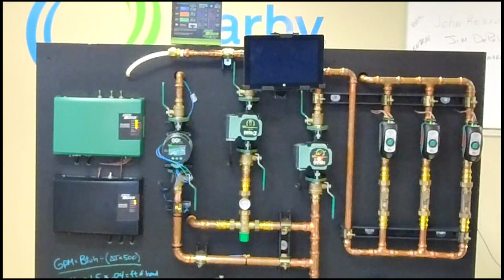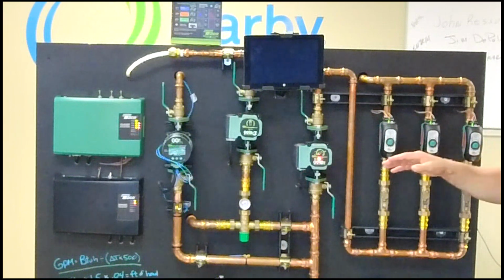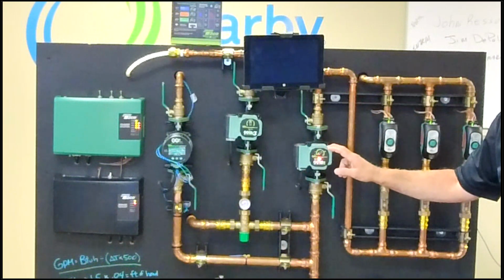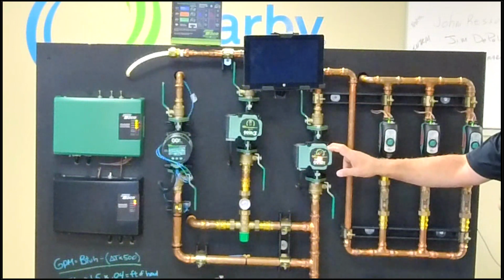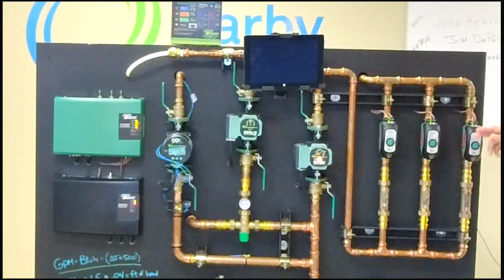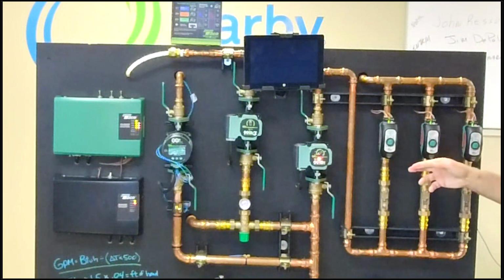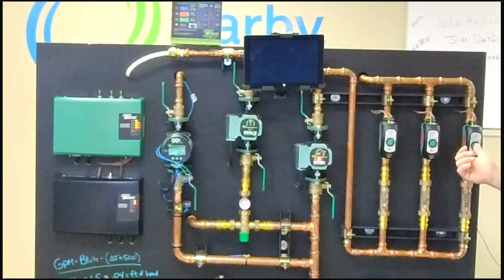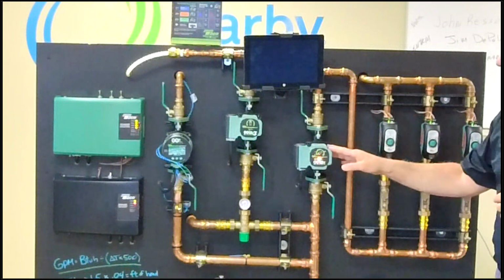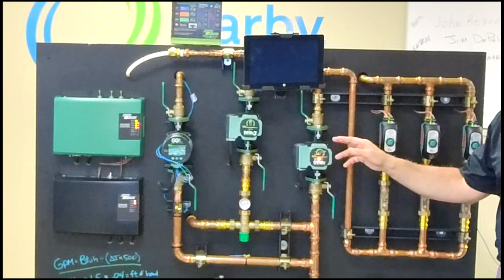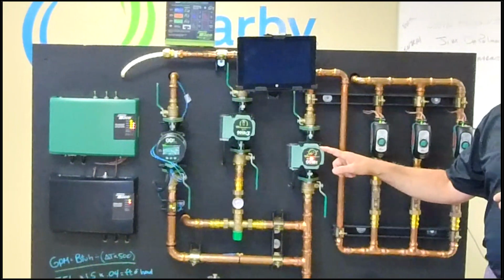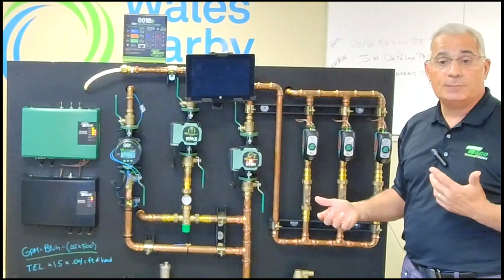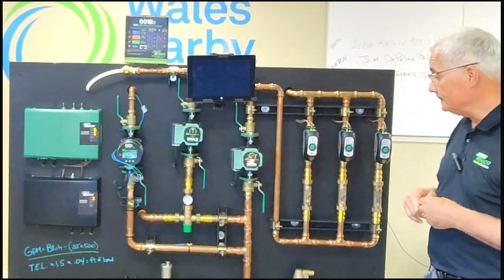The main focus of this webinar is showing you ECM product. What we're showing you here is that ECM product is going to use less voltage, less wattage, less amp draw, as will these zone valves. In a situation like this, I'm going to pull 0.06 amps per zone valve, 1.44 watts, I believe. And as I open and close these zone valves, I will be able to show you the actual wattage, or kW, that we're using here, and you'll be able to see the change of GPM and head as we open and close the valves.